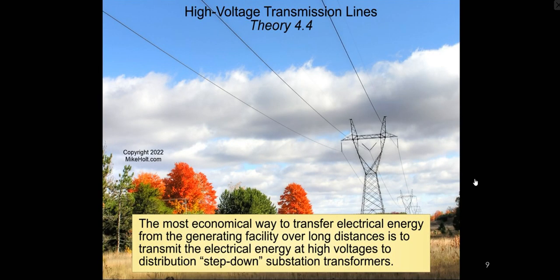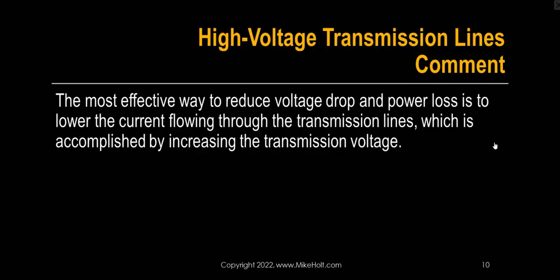High voltage transmission lines. The most economical way to transfer electrical energy from the generating facility over long distances is to transmit the electrical energy at high voltages to distribution step-down substation transformers. The most effective way to reduce voltage drop and power loss is to lower the current flowing through the transmission lines, which is accomplished by increasing the transmission voltage.